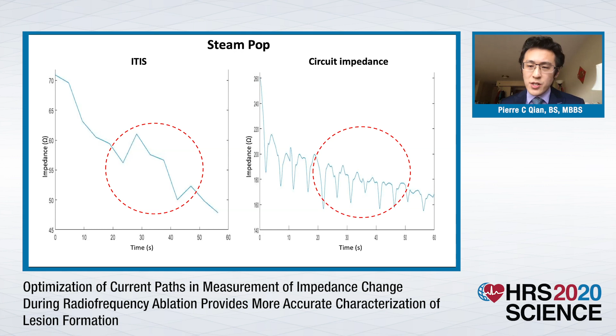In this study, we've demonstrated that it is possible to obtain cardiorespiratory gated 4-terminal impedance measurements during radiofrequency ablation using a combination of skin and intracardiac electrodes to optimize the current path for measurement. The impedance change thus obtained is better correlated with lesion dimensions compared with conventional ablation circuit impedance.